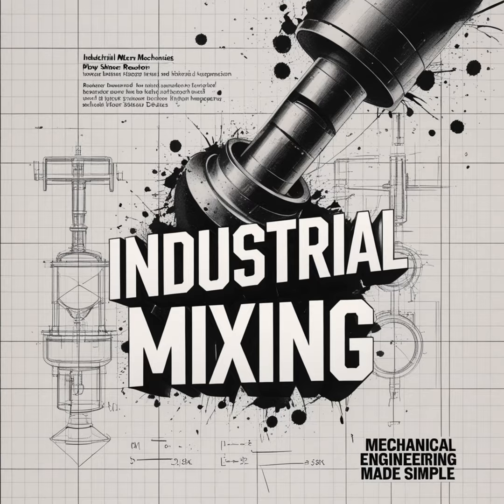It starts with the most critical fabrication step, welding. Welding requires mandatory quality checks throughout fabrication. You cannot just trust the welder's skill. Welding procedure specifications, or WPS, and their associated procedure qualification records, or PQRs, are required for all important seams. These documents detail exactly how the weld must be performed for every method used, MMA, MIG, submerged arc, or TIG.